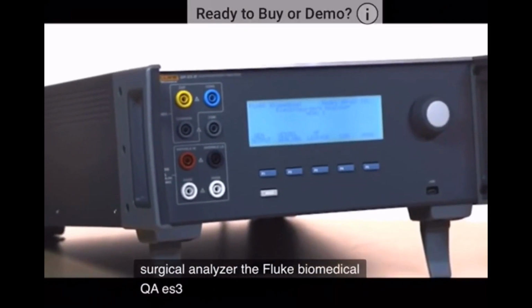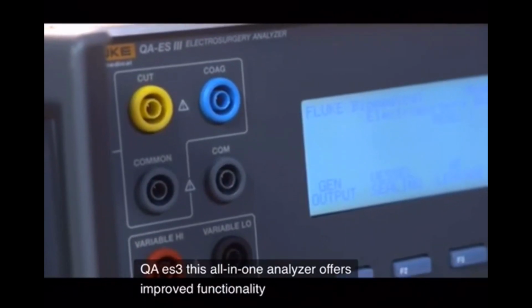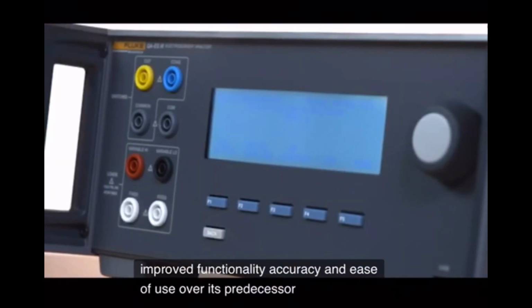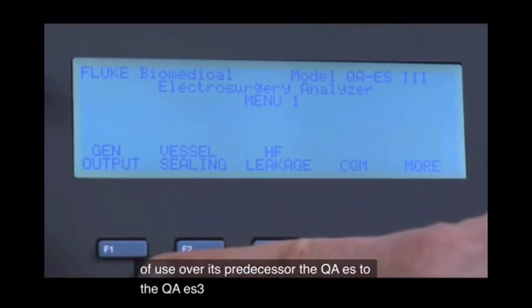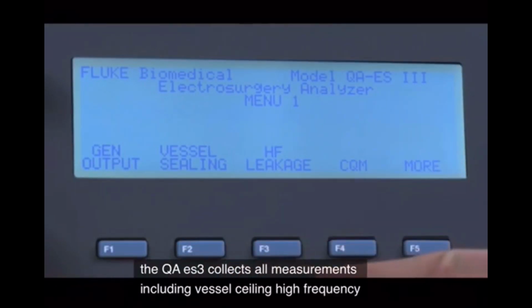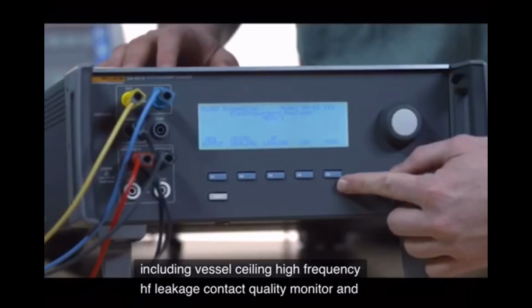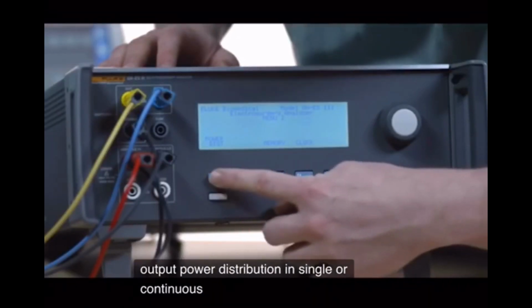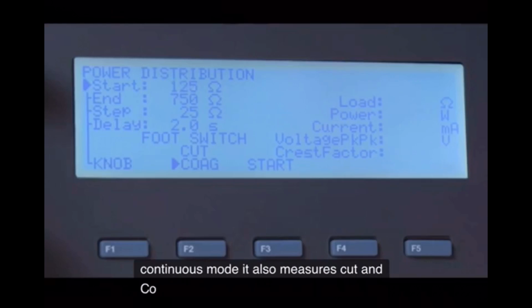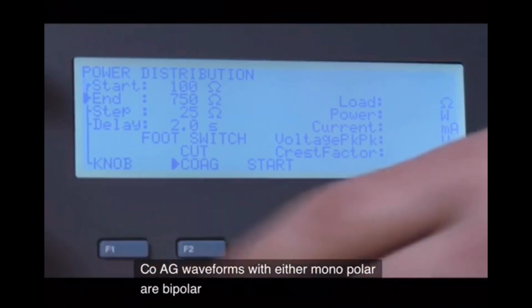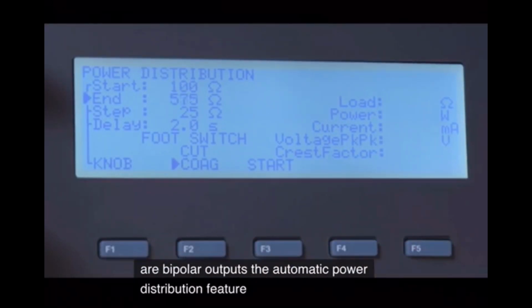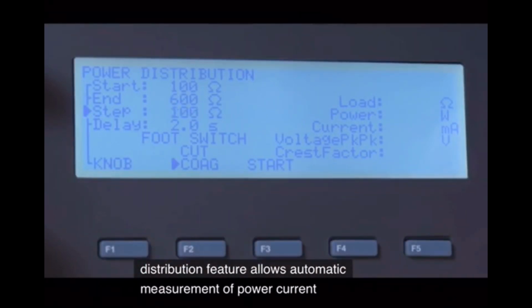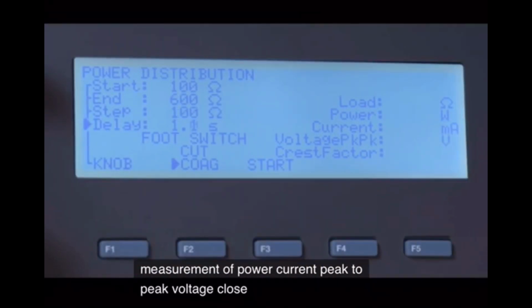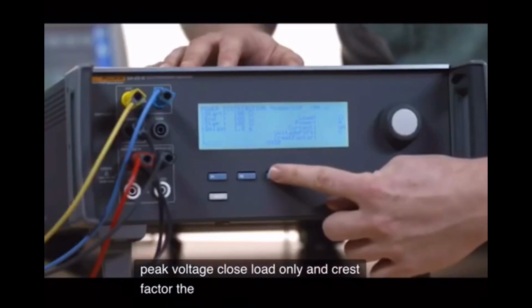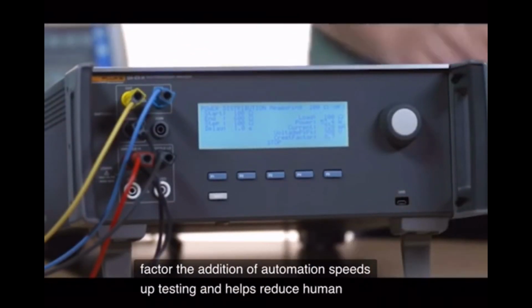Meet the next generation electrosurgical analyzer, the Fluke Biomedical QA-ES3. This all-in-one analyzer offers improved functionality, accuracy, and ease of use over its predecessor, the QA-ES2. The QA-ES3 collects all measurements including vessel sealing, high-frequency HF leakage, contact quality monitor, and output power distribution in single or continuous mode. It also measures cut and coag waveforms with either monopolar or bipolar outputs. The automatic power distribution feature allows automatic measurement of power, current, peak-to-peak voltage, closed load only, and crest factor. The addition of automation speeds up testing and helps reduce human error.